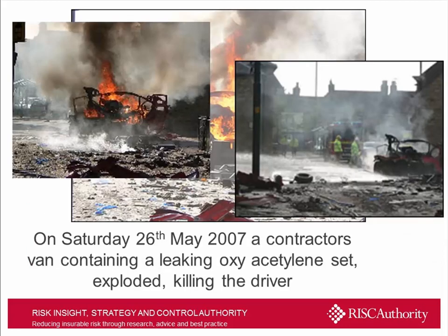There's a couple of photos there. I'm sure, sorry you can't see them all, but it's there just really to reiterate the concerns and the problems associated with the use of acetylene on site. There was a van carrying an acetylene cylinder or an oxyacetylene set that exploded, and you can see the damage that it did. We don't often get to see those sorts of images, except where these sorts of cylinders are being tested in a safe environment.